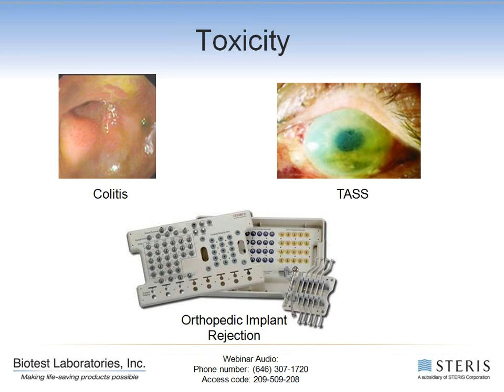And due to the buildup of residuals that can occur either due to lack of cleaning or lack of rinsing, for example, where you would have cleaning chemistry residues remaining, or even residues from water that's used to rinse these devices over time. Of course, the buildup of those materials, and then when that enters into the patient and remains for a certain amount of time, can lead to an immune reaction, and that can actually lead to the rejection of the device, something that may not be noticed for some months.